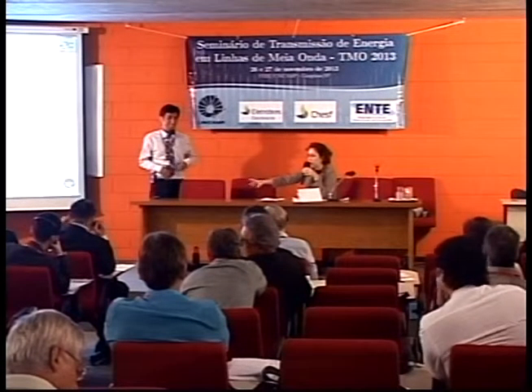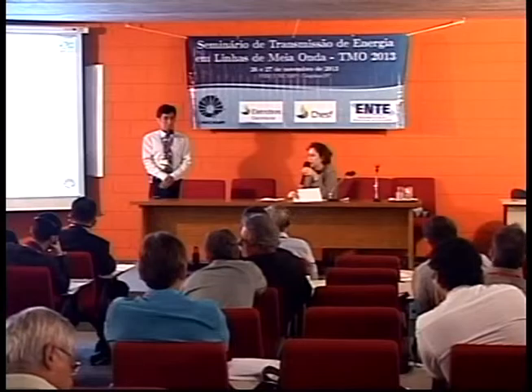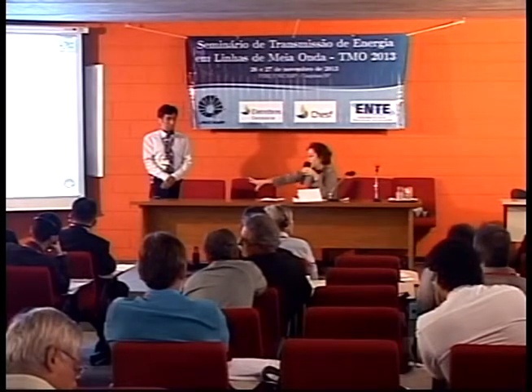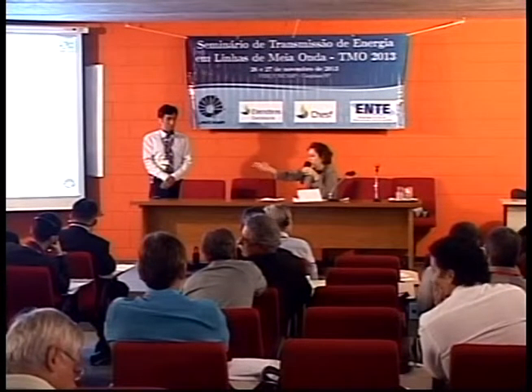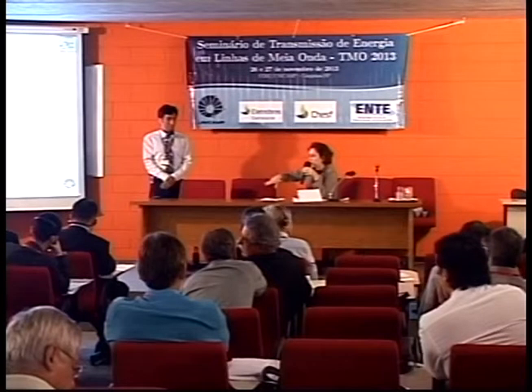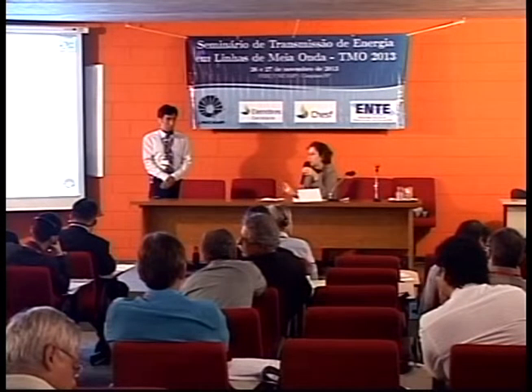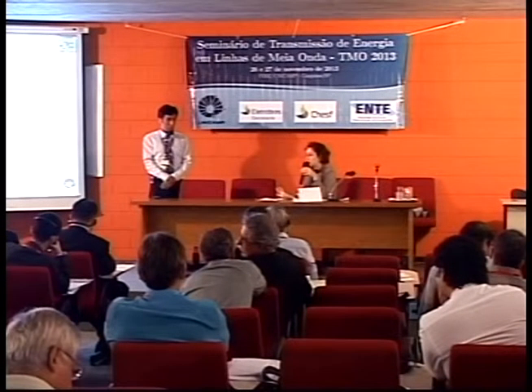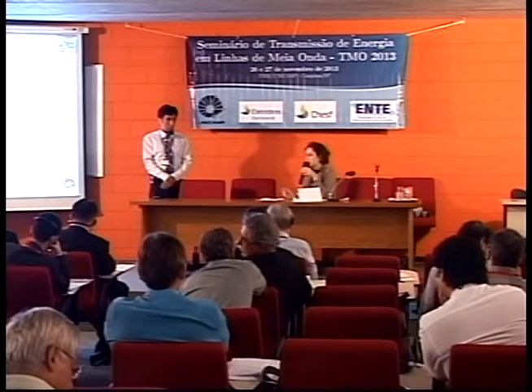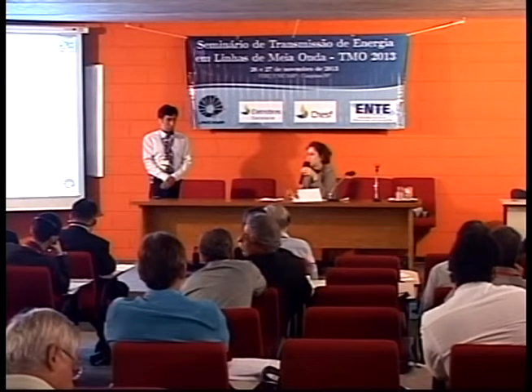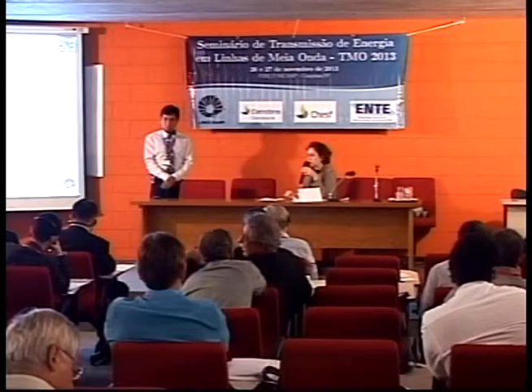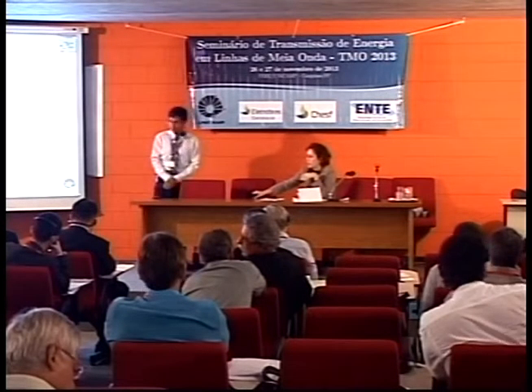Quite safely we could put some load at the end of the line, because the load would be a small one. Our line has 1,000 megawatts, the characteristic power of 1,000 megawatts, so some load in Bom Jesus wouldn't be that difficult to have. But you'd need some more negotiation. The no load test is already enough for us.